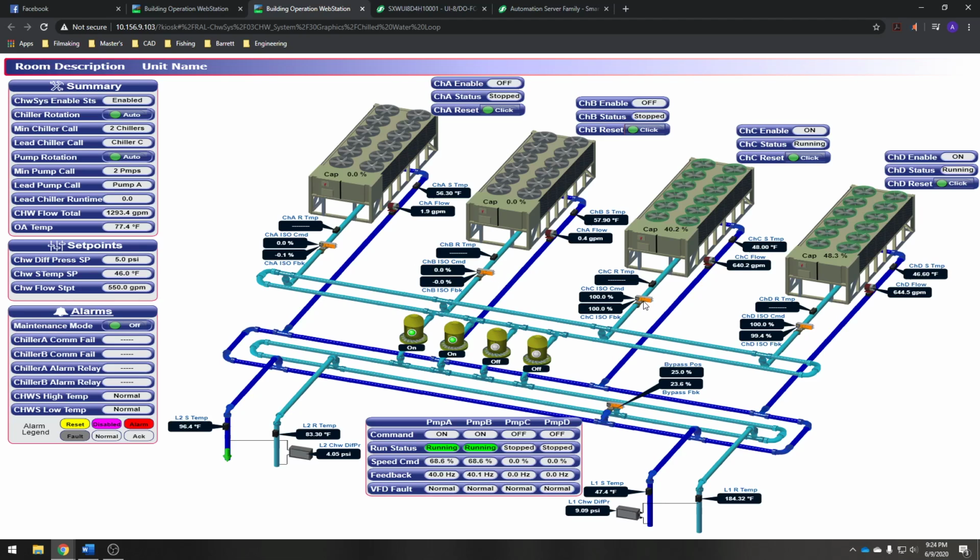So this is ultimately, again, what dictates whether this chiller runs or not. When this ISO valve feedback gets above 80, the end position switch is going to close and tell the chiller, hey, let's start, and it'll start staging up. If this valve is less than 80, it's telling the chiller, hey, shut off. It's as simple as that.